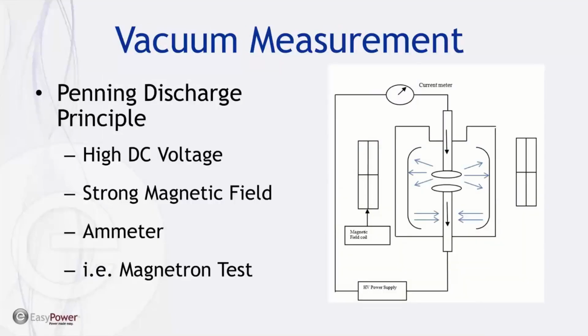So when these vacuum interrupters were developed and manufactured, the manufacturers needed a technique for measuring the vacuum inside. And the way that they do that is with the Penning discharge principle. In the Penning discharge principle, you apply a high DC voltage across the open contacts of the vacuum interrupter. Just doing that, nothing special happens. It's just like a DC high pot. You have some amount of leakage current. That leakage current corresponds to electrons that are traveling from one contact to the other through the vacuum.